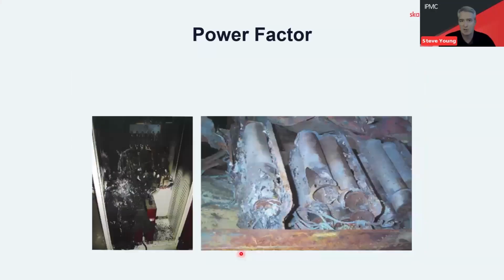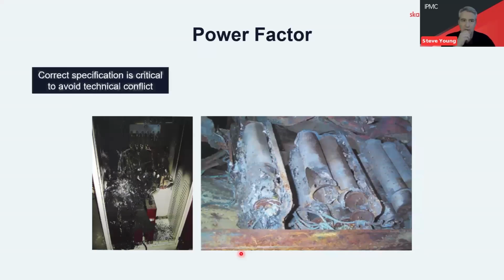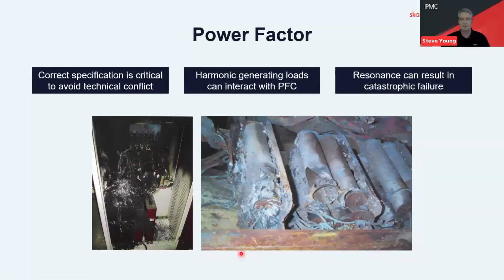So the image here and the little notes above are pointing at the very real risk of technical conflict. I saw 4 of these across a 12-month period. Obviously not while I was there, fortunately, but you get called in to investigate, post-incident root cause analysis, if you like. It's very common to have a technical conflict between harmonic generating loads on site and unprotected capacitors. And unfortunately, whilst there are systems in place that should hopefully let these things trip automatically and safely, it really isn't always the case. So we need to consider mitigation, which Tony's going to talk to us about, and what we can do about that.